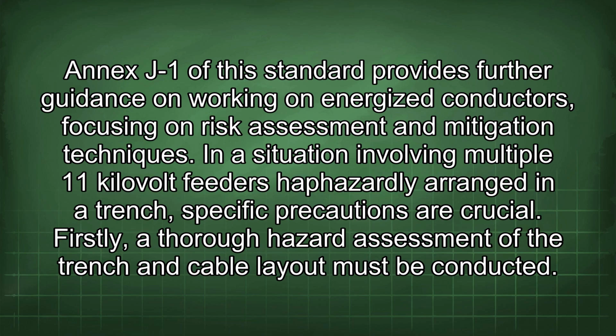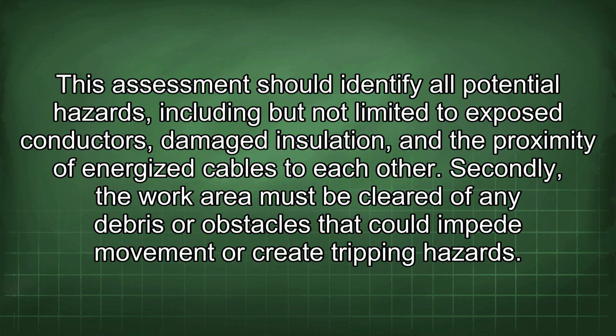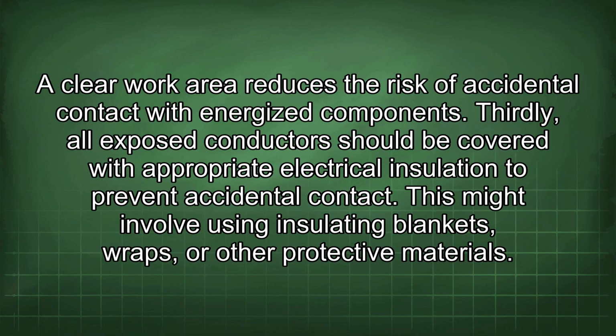In a situation involving multiple 11 kV feeders haphazardly arranged in a trench, specific precautions are crucial. Firstly, a thorough hazard assessment of the trench and cable layout must be conducted. This assessment should identify all potential hazards, including but not limited to exposed conductors, damaged insulation, and the proximity of energized cables to each other. Secondly, the work area must be cleared of any debris or obstacles that could impede movement or create tripping hazards. A clear work area reduces the risk of accidental contact with energized components.